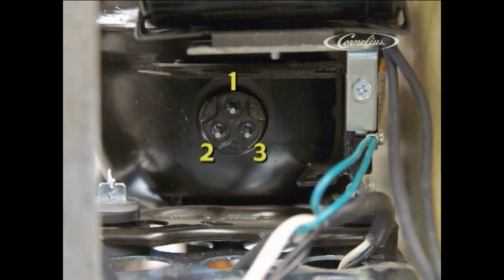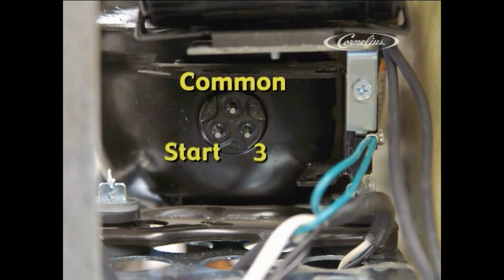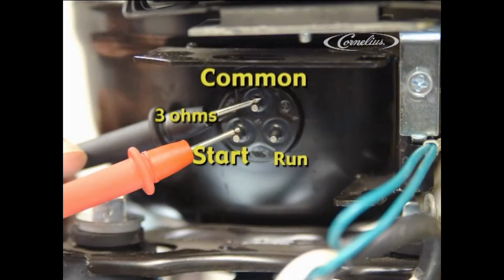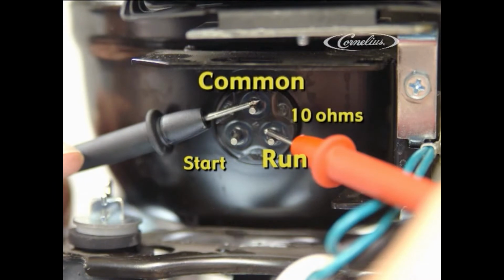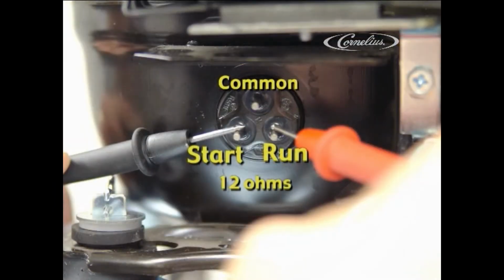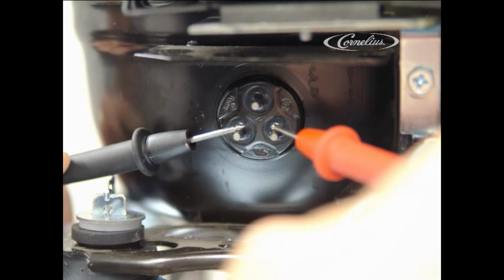You now see these 3 pins. The top pin will be referred to as the common pin. The left side is start and the right side is run. Now we will measure the resistance across these pins. Common to start should be about 3 ohms, common to run should be about 10 ohms, and run to start should be about 12 ohms. If any of these read 0 ohms or infinity, then the compressor will need to be replaced.